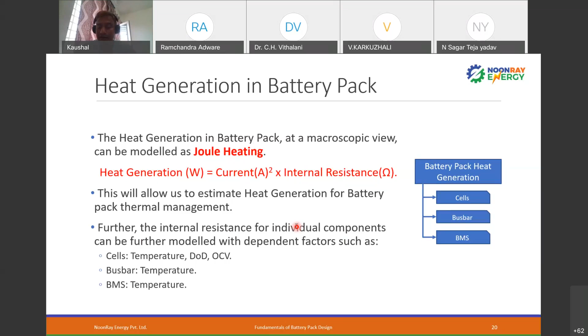Further, this internal resistance is not a constant. It keeps changing depending upon the temperature, depth of discharge, open circuit voltage, busbar temperatures, BMS temperatures. But if I have to do a first-hand calculation, I'll always do it with current squared times internal resistance.